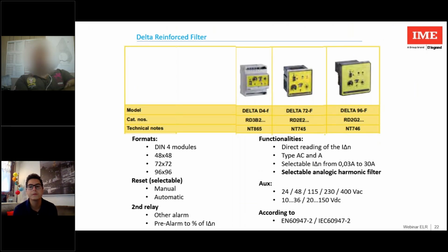In our range, we have some relays with a reinforced analog filter. What does it mean? If you have a sinusoidal waveform line, which therefore falls under the type A or AC, but is characterized by a strong harmonic component, a normal relay could have an untimely trip or generate a false alarm. This filter cleans the waveform of the harmonic component and helps in many cases where I have untimely trips.